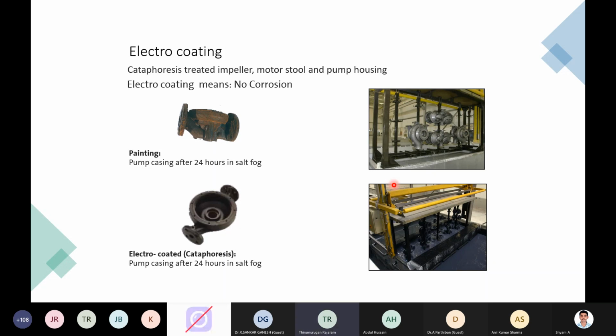Yes, there are many corrosion resistance coatings available, so that we can decide and take a call on the product itself. Because if you have a very large pump and a challenge of corrosion, obviously you can invest in it and extend the life of the casing. Because if a casing fails, meaning the casing is completely corroded, obviously that becomes a huge capex for you. So all that you can avoid with this kind of coating solution.